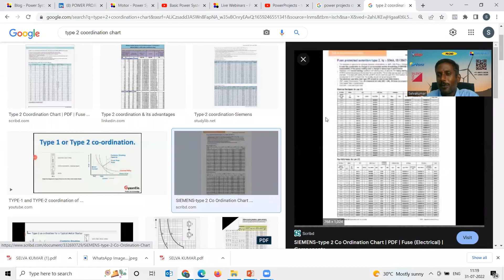Let me quickly put some type 2 coordination chart images for some motors. That has an advantage, like you can know the minimum capacity of the motor, the maximum capacity of the motor, what is type 1 coordination, what is type 2 coordination, and why we have to go for type 2 coordination.